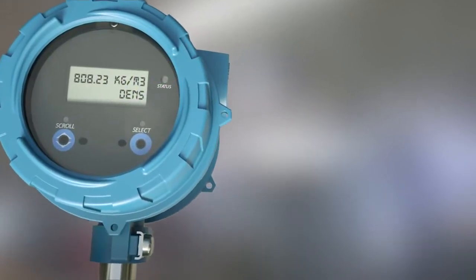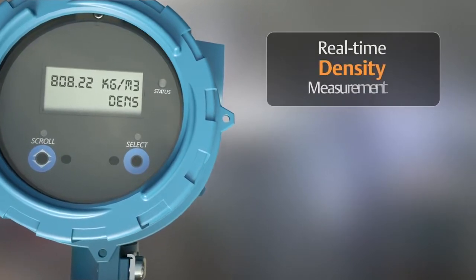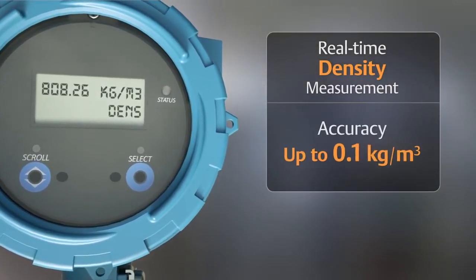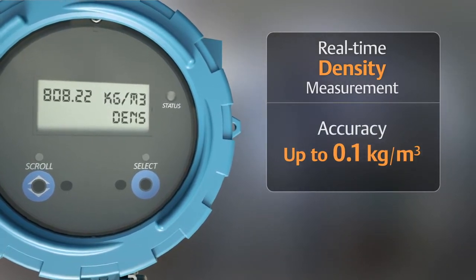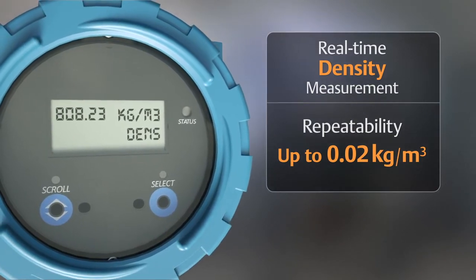Let's look at some of the key features of the Compact Density Meter. The meter provides real-time, inline density measurement with up to 0.1 kg per cubic meter density accuracy and up to 0.02 kg per cubic meter density repeatability.